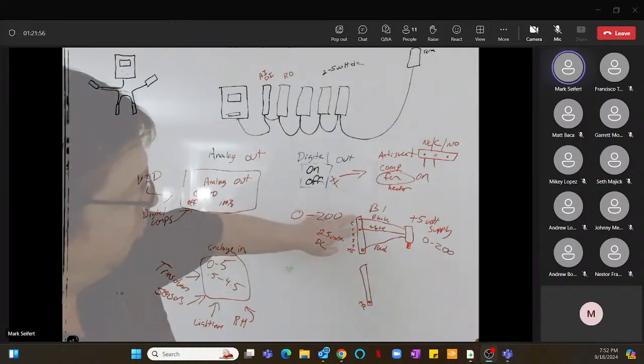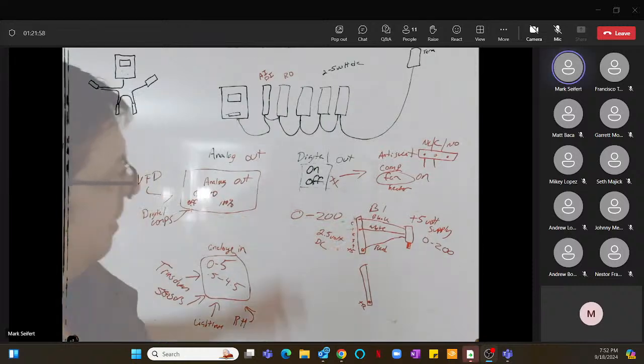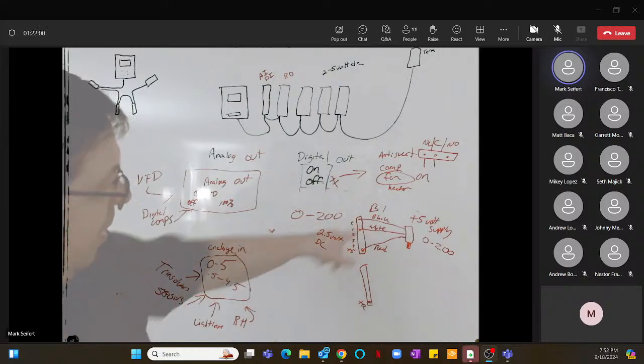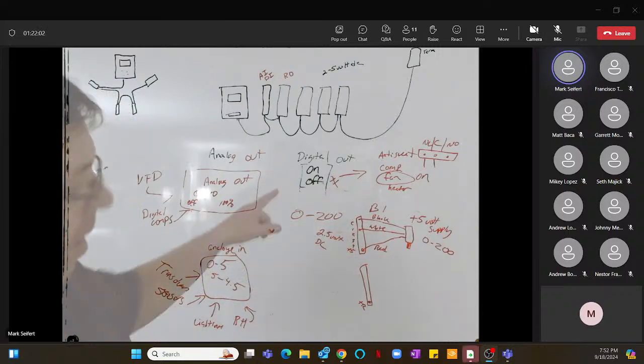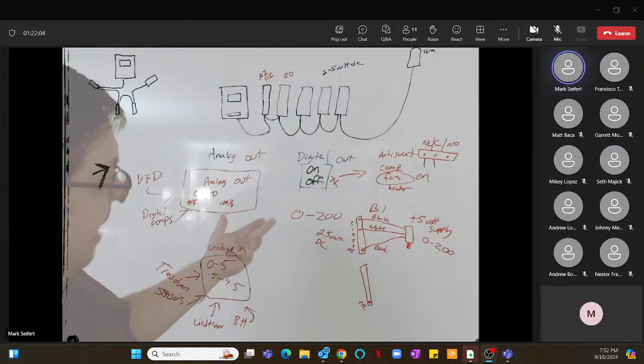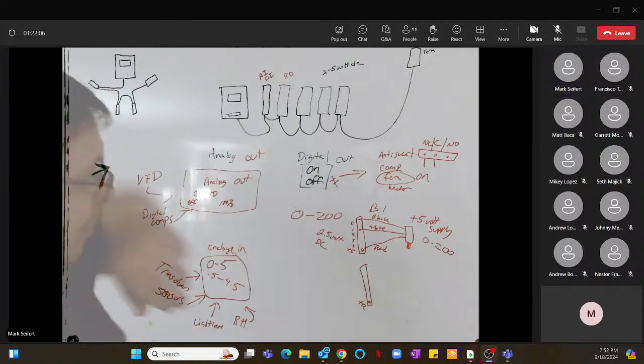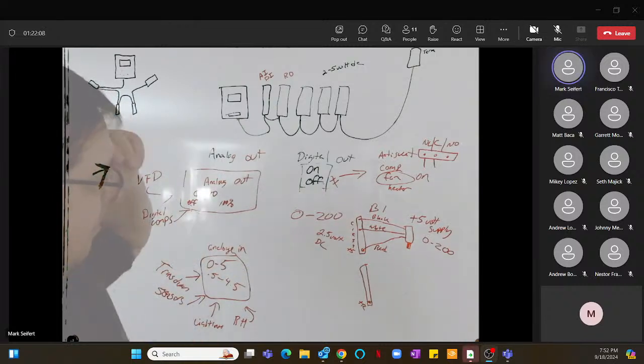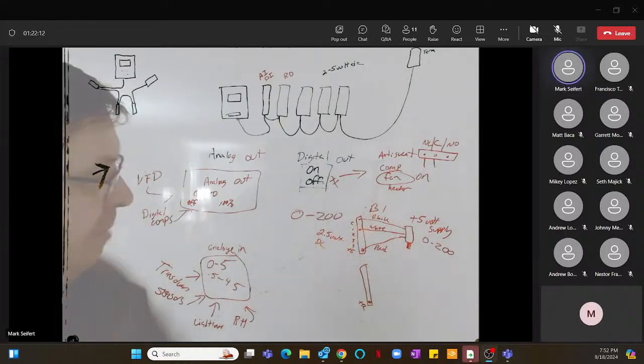If you have 2.5 volts between the black and the white, that thing should be reading 100 PSI on your controller. If it's not, there's a problem. You'll need to calibrate it. Or the transducer could be bad too.